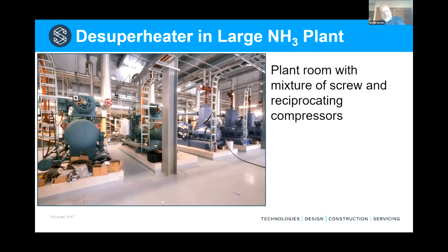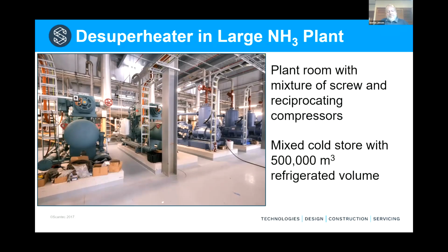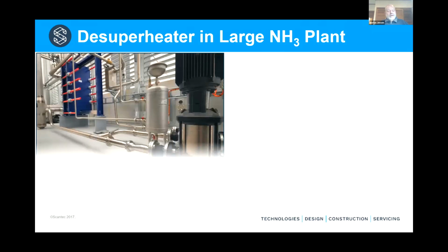Then we come to this bespoke ammonia plant that runs a 500,000 cubic metre cold store in Queensland. So we have a mixture of compressors here. On the left, you can see some screw compressors, and on the right, you see some reciprocators. We are recovering heat from the reciprocating compressors. They sit on the second compression stage. Screw compressors sit on the first compression stage.